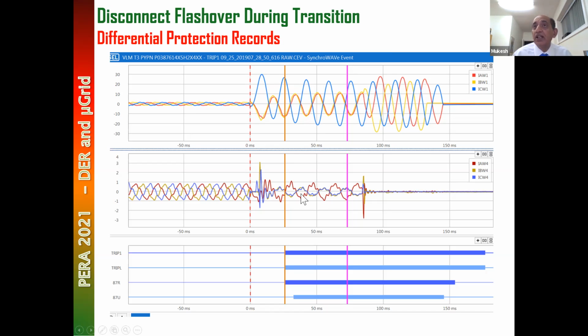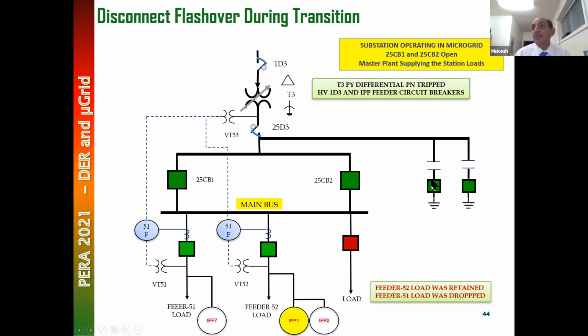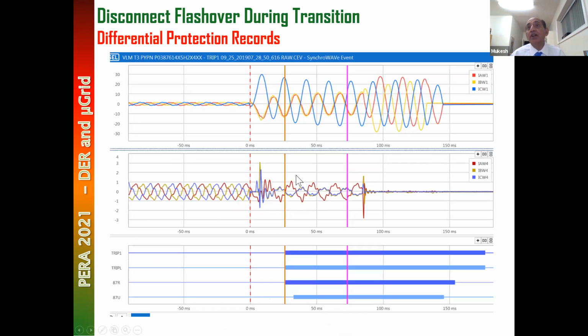Why? There was a lot of third harmonic here. What we discovered after this fault was that this capacitor was tuning the system. There's a system connected here. The capacitor was tuning third harmonic. They were sucking it up. They were forming a third harmonic filter. They were not filter capacitors. They were purely power factor capacitors for the station. But they were also acting like a third harmonic filter.